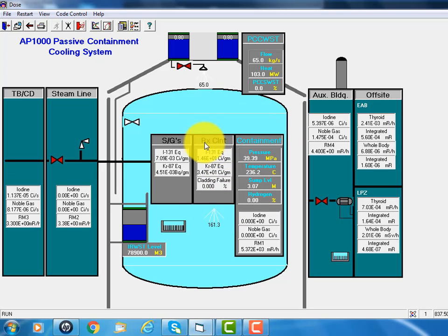The primary coolant goes to the primary containment, so the steel shell becomes very hot. The containment spray is actually spreading outside the liner from the tanks at the roof of the containment. The containment is built of reinforced concrete.